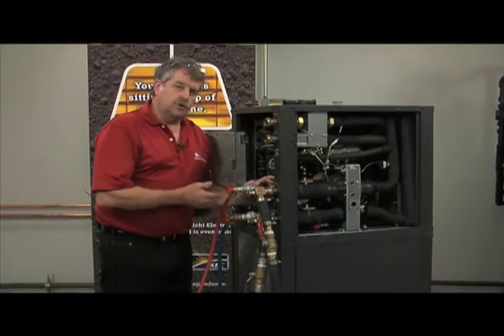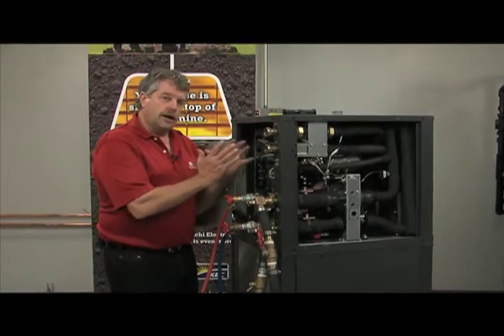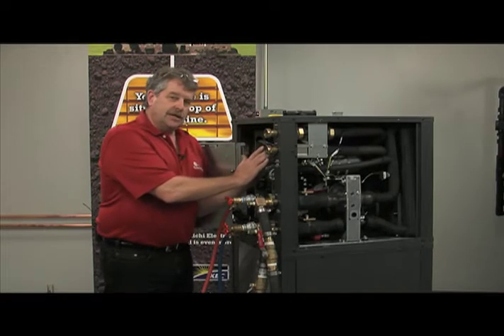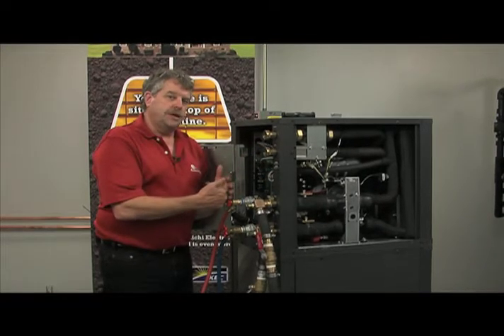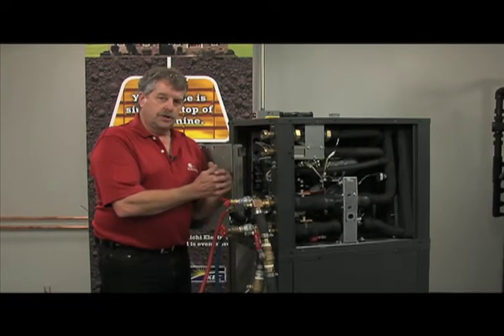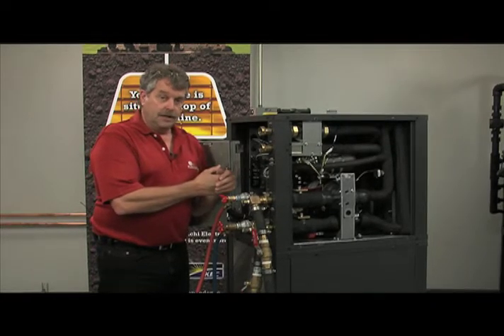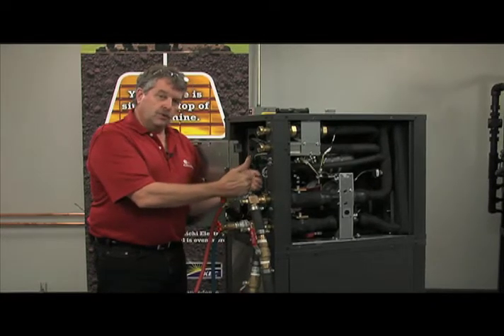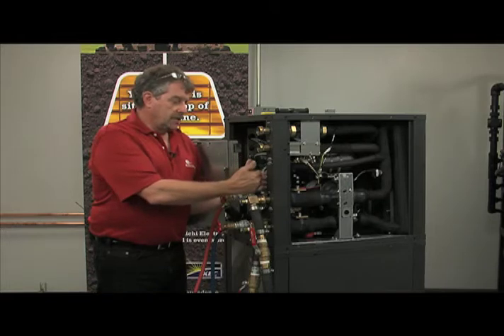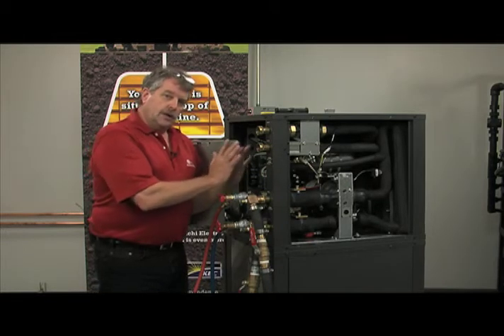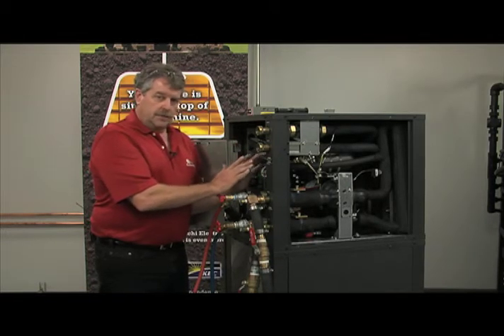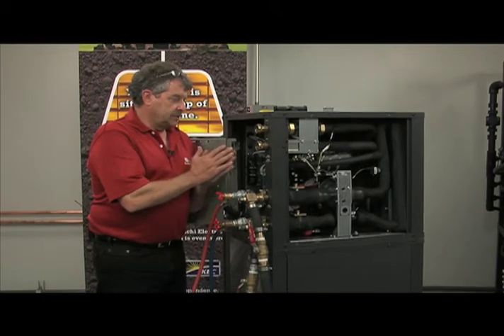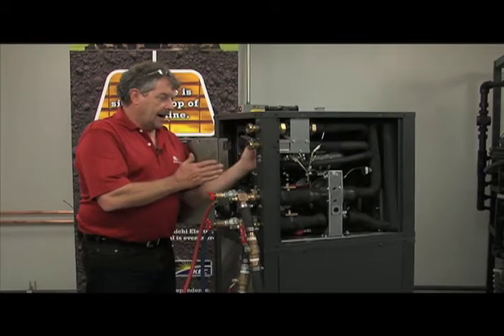Have yourself a bucket so you can capture the fluid. We're just going to knock the pressure down inside the heat pump. We don't have to take the entire loop down because we're just doing some work in here on the loop side. So we have the ability, with the V-Flow only, to come in here and isolate that loop, knock down the pressure inside the heat pump, and get after some of these replacement components.